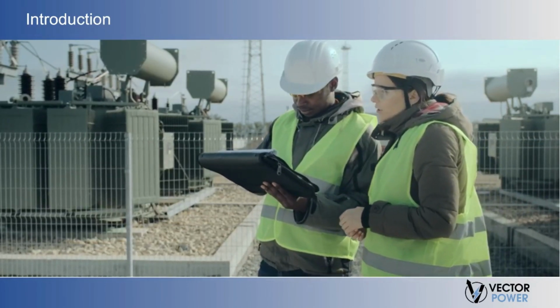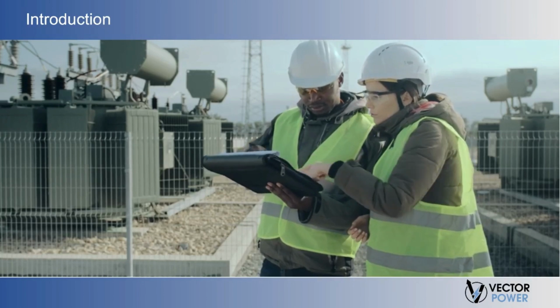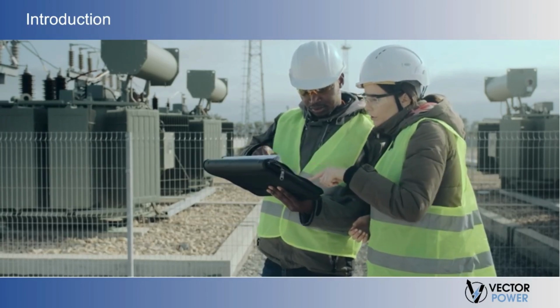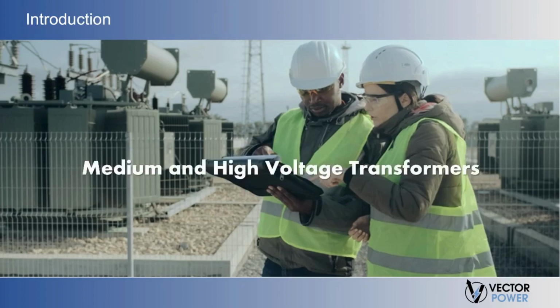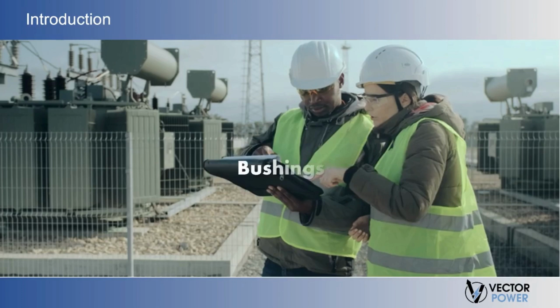Now, technicians that can properly perform and evaluate the results of power or dissipation factor tests can predict and prevent the failure of medium and high voltage transformers, circuit breakers, bushings, reclosers, switches, cables, lightning arresters, liquid insulation, potheads, rotating machines, and voltage regulators, just to mention a few items.